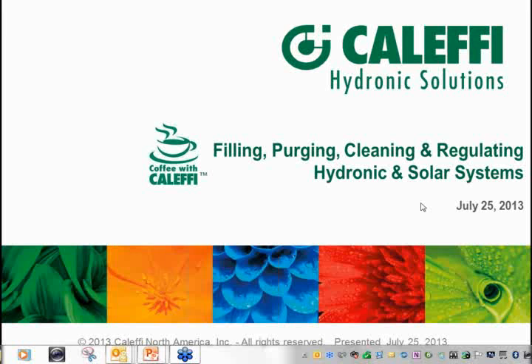Now, filling and purging, I kind of broke that down. Obviously, every system is going to have to be filled. I mean, the only way you can turn on the system and start running is filling it. Purging gets done to a pretty good point. I would say most people purge to the point where their pumps are going to work and they're moving fluid and they're moving heat or they're moving the energy through the system.